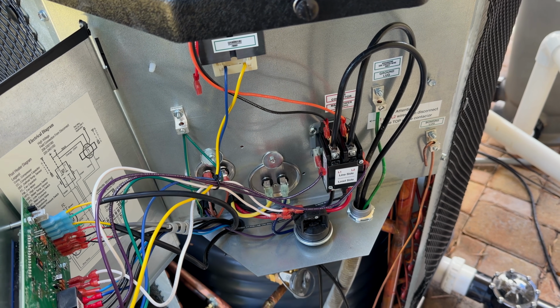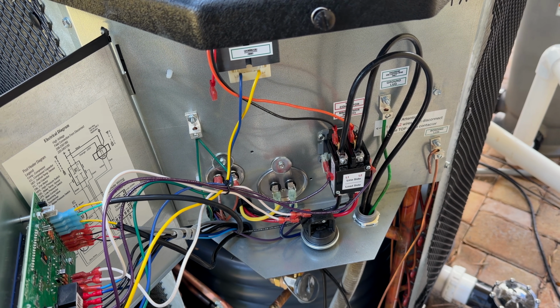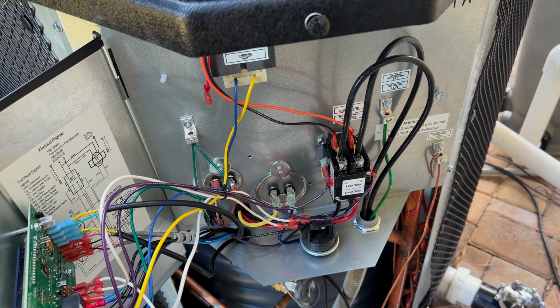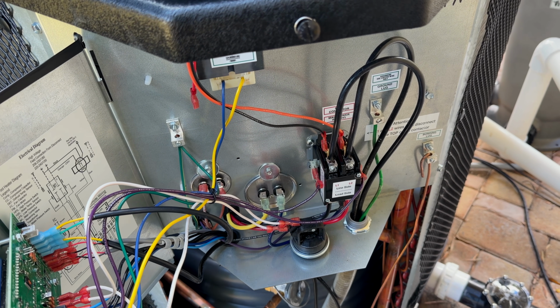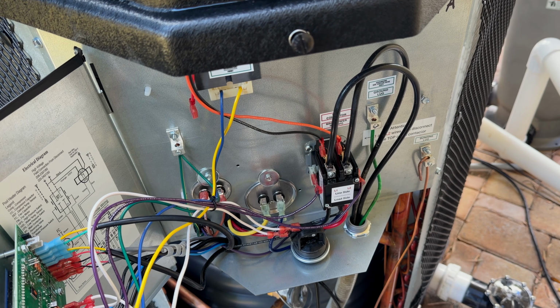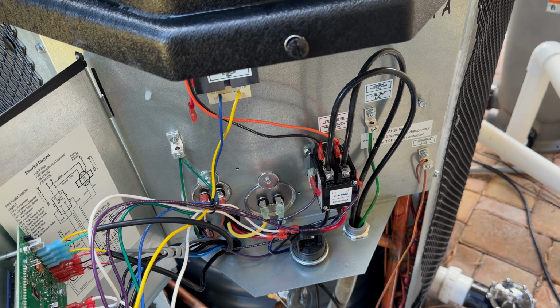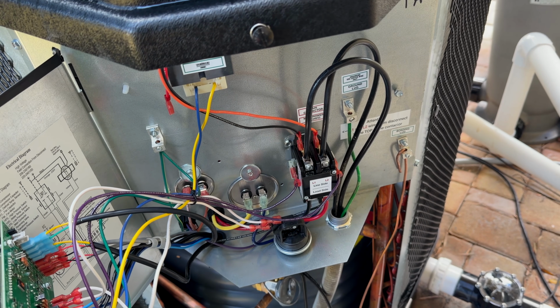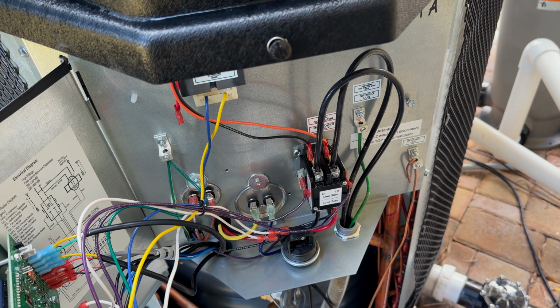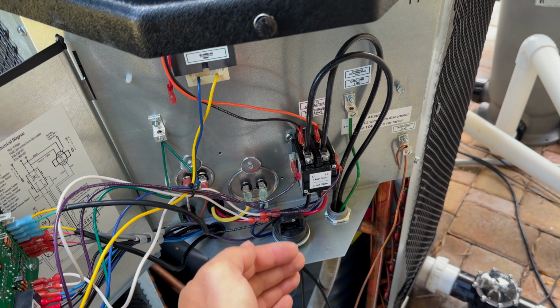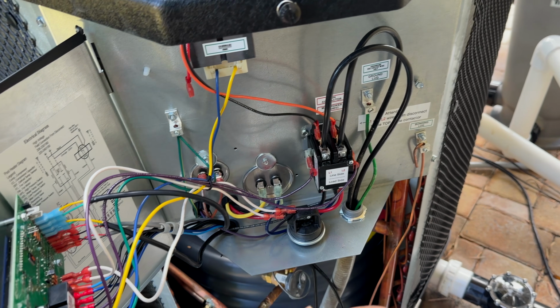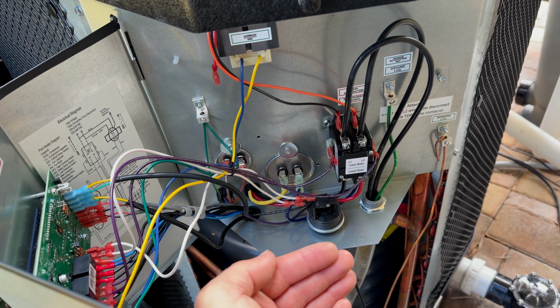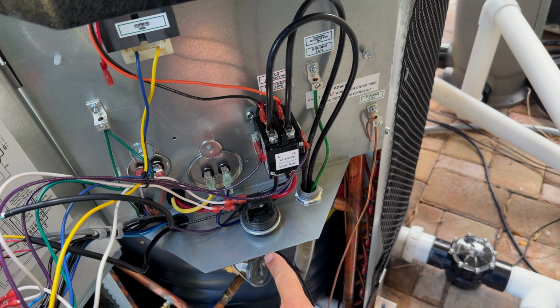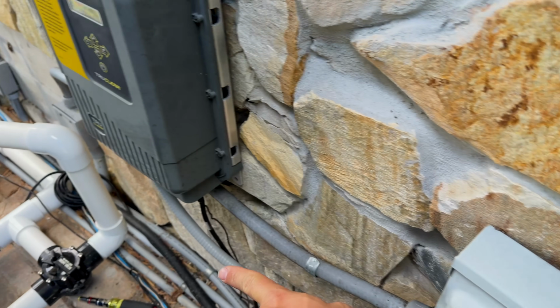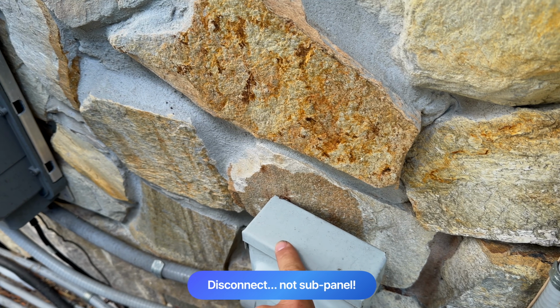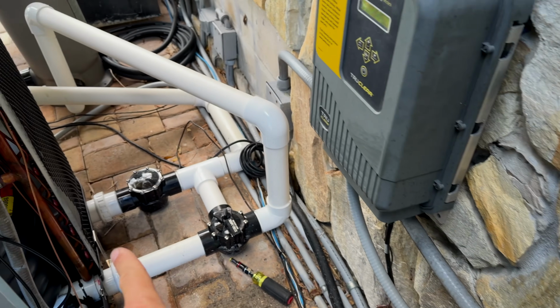Alrighty, so now you guys can see I am inside of the electrical compartment of the Gulfstream heat pump. But before we get started and show you where all the wires go, let's talk about code for a second. The NEC states that if you're wiring a timer box, an automation system, a sub panel, a heat pump just like this, there needs to be 36 inches of unimpeded space from the working face of that box outward. In other words, 36 inches from this, where my hand is, out towards the camera. So from here, I measured directly across to this sub panel, and it's exactly 37 inches. So I met that code here. It's very important to follow that.